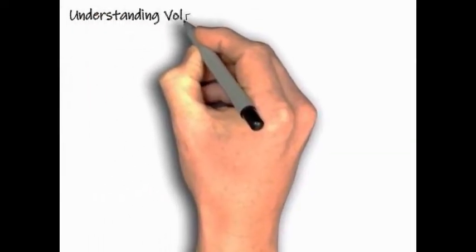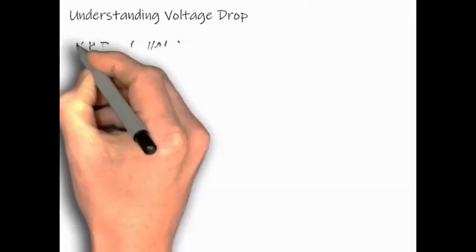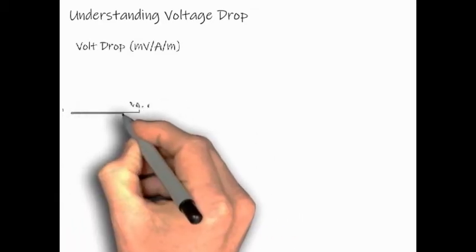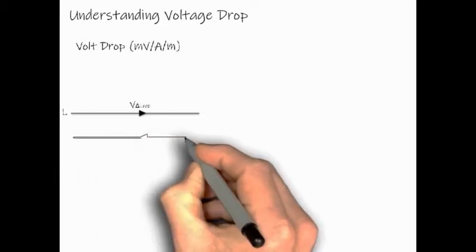Next, we're going to talk about voltage drop. Voltage drop can be represented in millivolt per ampere and per meter. The voltage drop can be calculated by finding the voltage difference on the conductors. For example, this can be done by adding the voltage difference between the live cable and neutral cable.